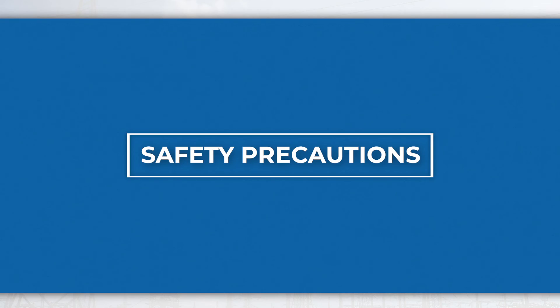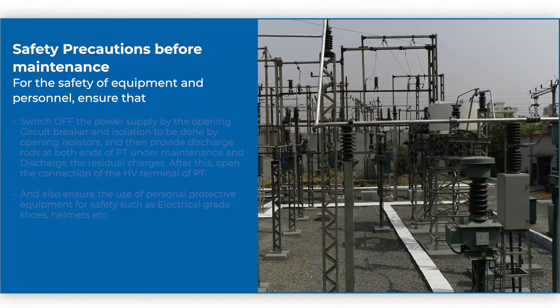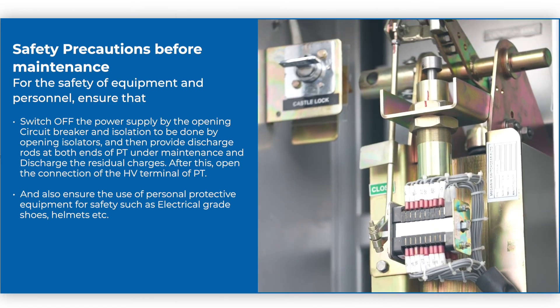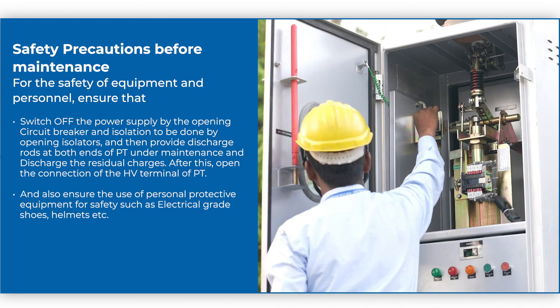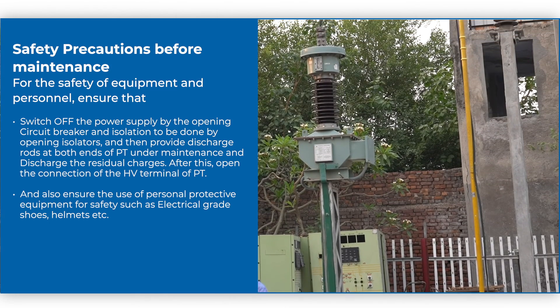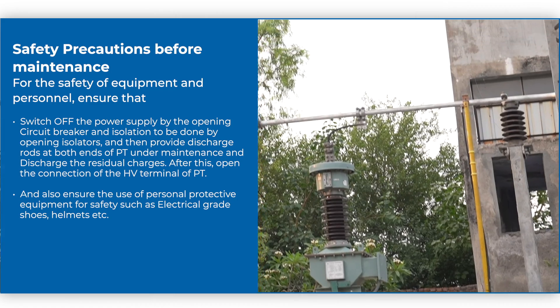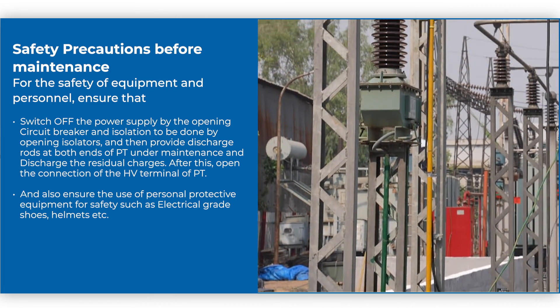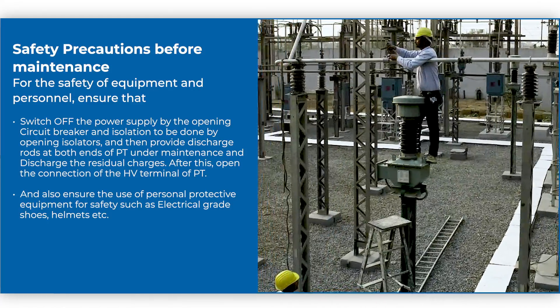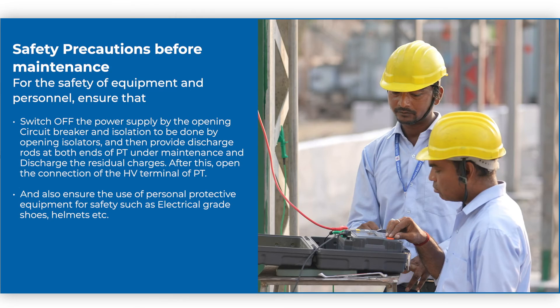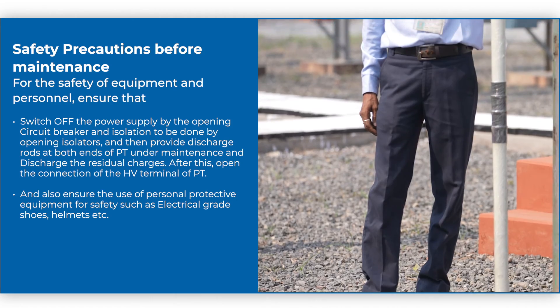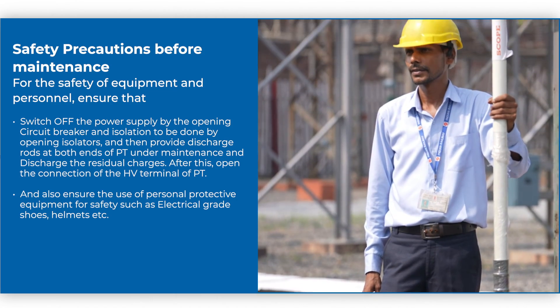Safety precautions before maintenance: For the safety of equipment and personnel, ensure that the power supply is switched off by opening the circuit breaker, and isolation is done by opening isolators. Then provide discharge rods at both ends of PT under maintenance and discharge the residual charges. After this, open the connection of the HV terminal of PT. Also ensure the use of personal protective equipment such as electrical grade shoes, helmets, etc.